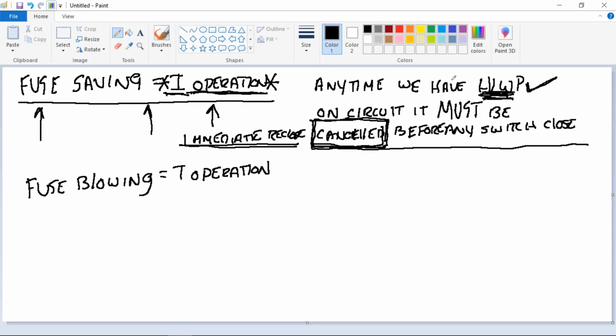Okay. In non-automatic, with a hotline work permit, you're going to get that instantaneous open. The breaker's not going to reclose with a hotline work permit. And then there's going to be a lot of unhappy people. But if there was a fault, though, wouldn't it eventually stay open? No, it's still going to have the time cycle, buddy. It's still going to blow the fuse. We're going to go to the time cycle.